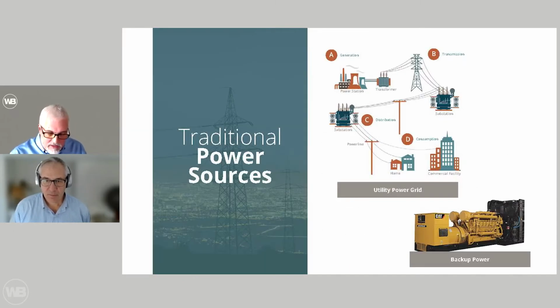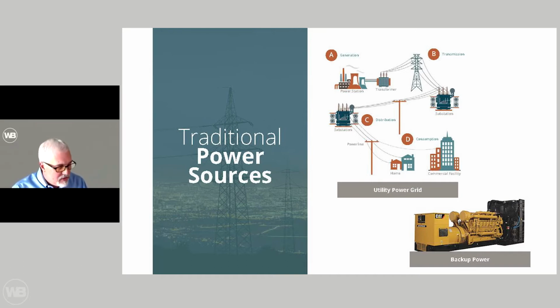Traditionally, when you look at our data center world, our primary source is the utility grid, and then we go to backup power as a diesel generator. Diesel generators have been the workhorse of our industry for years. They're very reliable, they can take the transient loads, we can drop block loads on them, and they start quickly. But they are a necessary evil.